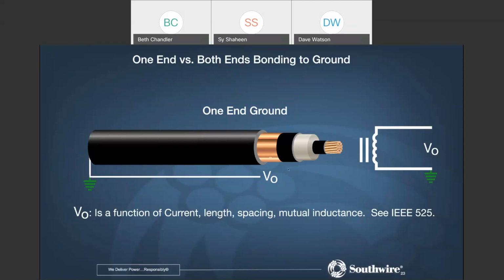I have a termination. Well, when you look at a cable, while it looks very simple in construction, from an electrical standpoint, it's really amazing what different things go on within a cable. So I have this energized at 60 hertz. It's carrying a lot of current. I have this tape shield on it. Really what it's acting as is a transformer with a 1-to-1 ratio, because I have current coming in here. It's inducing a flux onto this tape shield, and it becomes a transformer, just like I show it here.